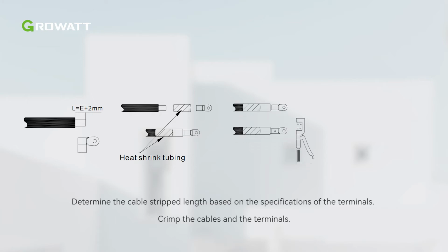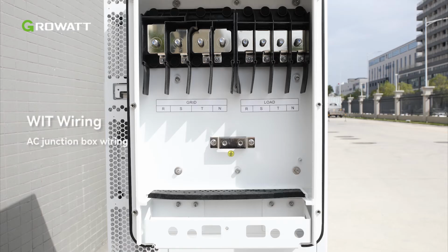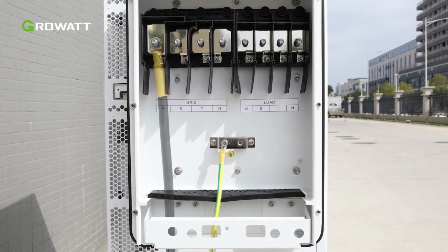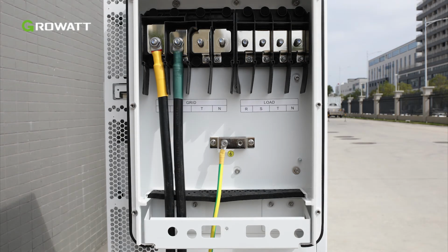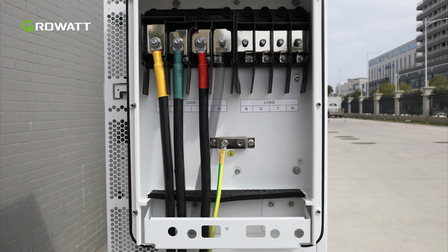18 to 22 mm is recommended. Crimp the cables and the terminals. First, connect the ground cable to the copper grounding bar in the AC junction box. Then we need to connect the main power cables according to the label.